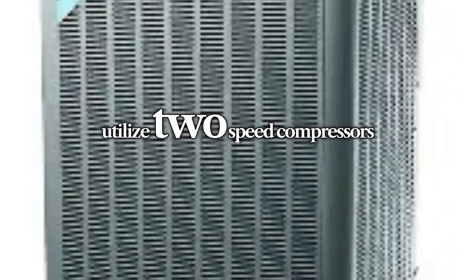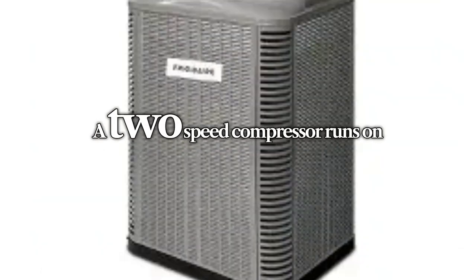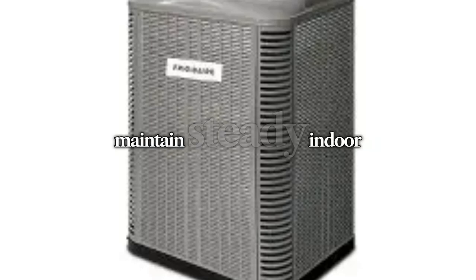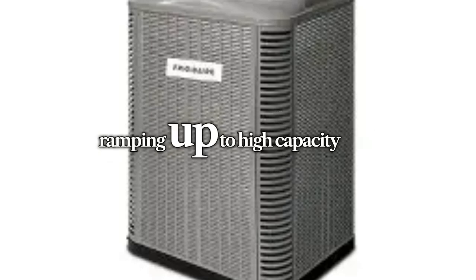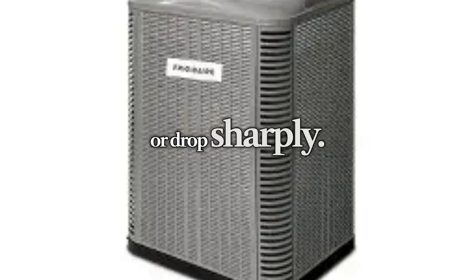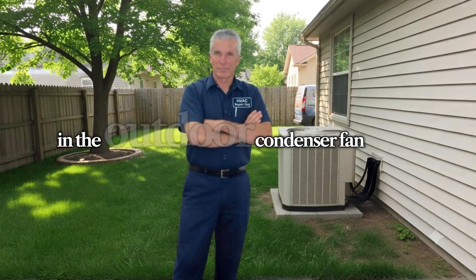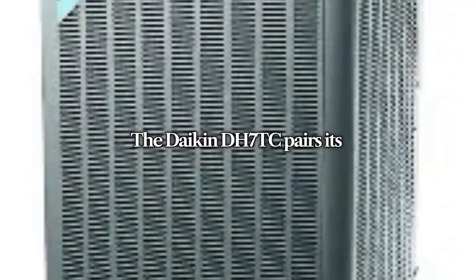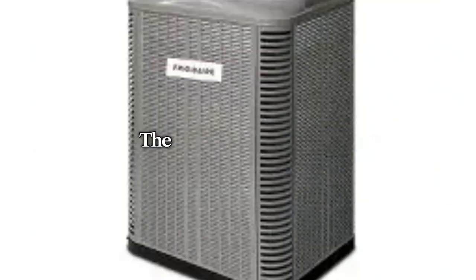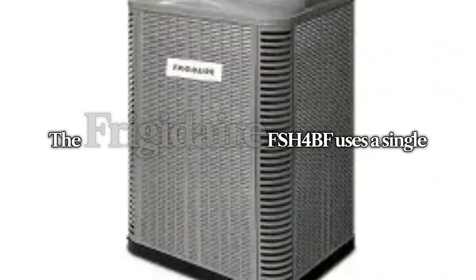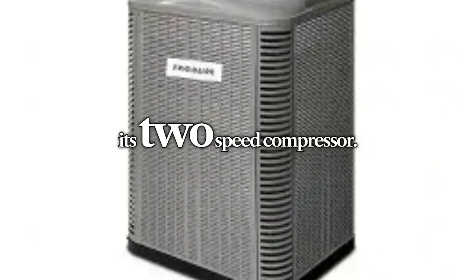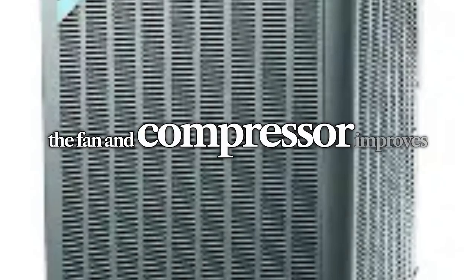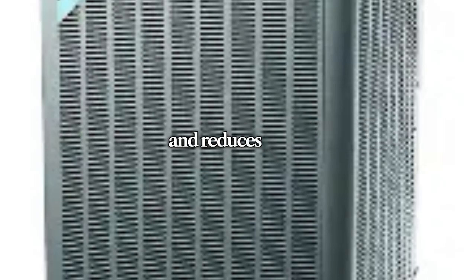Looking under the hood at compressor and fan design, both systems utilize two-speed compressors rather than single-speed or fully variable speed inverter compressors. A two-speed compressor runs on low capacity most of the time to maintain steady indoor temperatures and manage humidity, ramping up to high capacity only when outdoor temperatures spike or drop sharply. Where these two differ is in the outdoor condenser fan motor. The Daikin DH7TC pairs its two-speed compressor with a two-speed condenser fan, allowing outdoor airflow to match compressor output. The Frigidaire FSH4BF uses a single-speed condenser fan alongside its two-speed compressor.